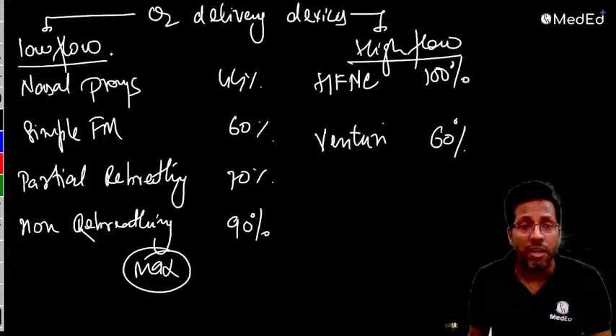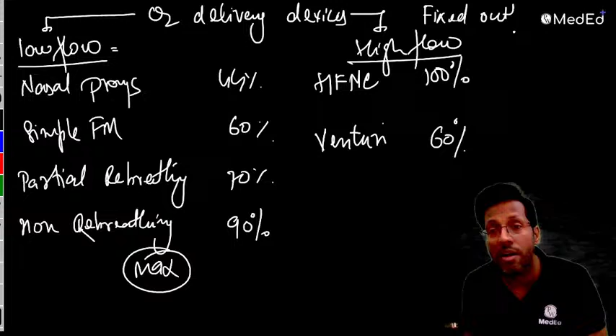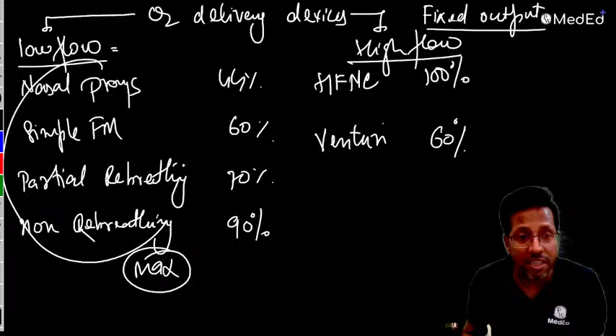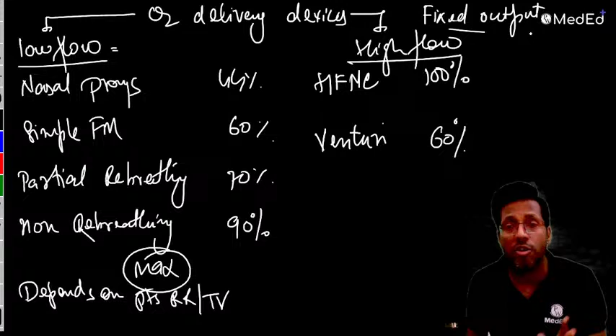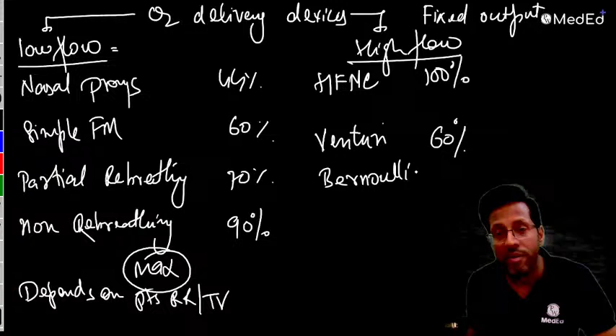So what's the difference between them? In the low flow device and the high flow device, the point is the high flow devices normally are the ones which give you a fixed output. You know how much is going to the patient actually by how much you've started. It does not depend on the patient's respiratory rate. All of the low flow devices normally depend on the patient's respiration, on the patient's tidal volume, patient status, patient's ventilation. But high flow is going to deliver irrespective of that. They are fixed output devices. In fact, Venturi mask is based on Bernoulli's law, air entrainment, Venturi principle.